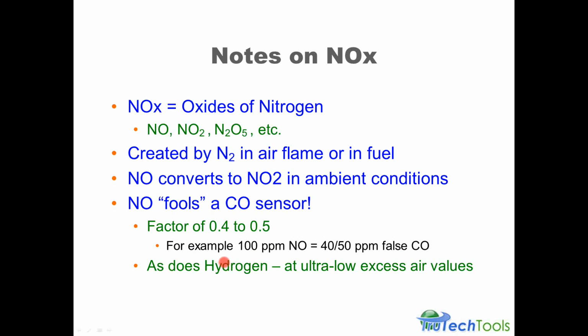One other point, hydrogen does cause a cross interference on a CO sensor, but that's usually not an issue unless you're at ultra low excess air values, and that means very high efficiency burners, that kind of thing. That's only where you're going to see this hydrogen issue. So there are special sensors that deal with the hydrogen concentration, but they're usually not of note or of value in the burner boiler and residential testing market.